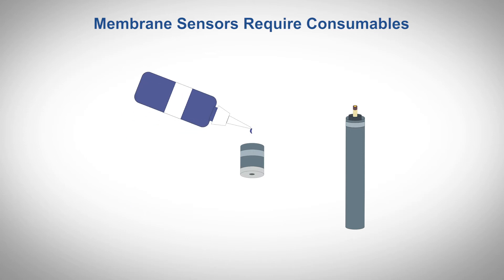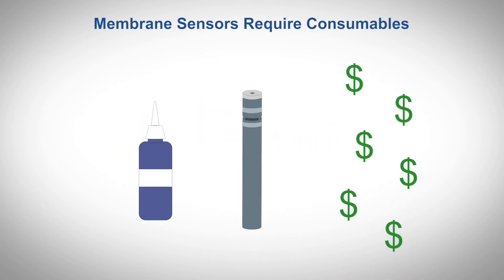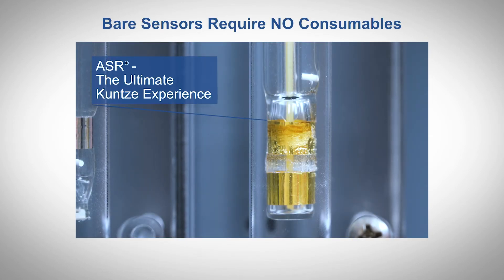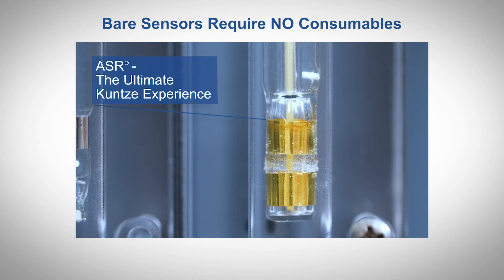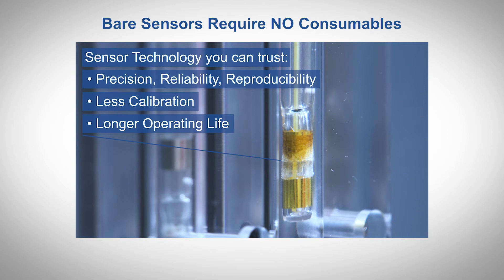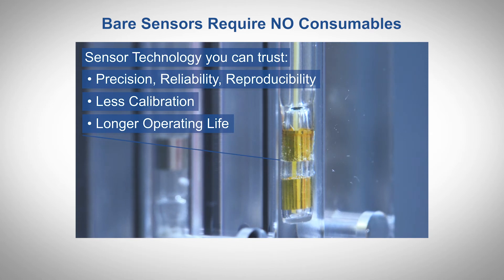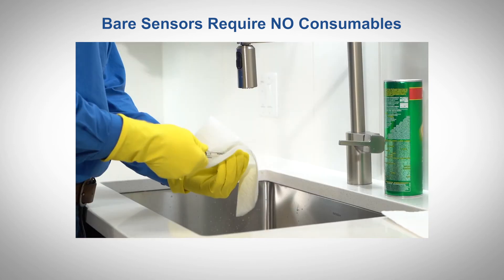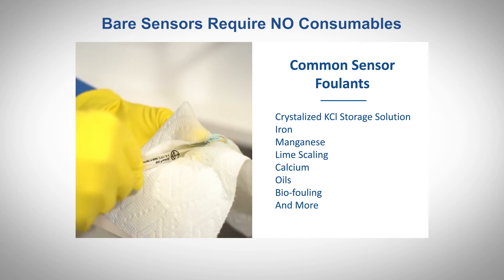Periodic refilling of the electrolytic gel over the reference and measuring electrode is also required. Kuntze's bare sensors do not require consumable components or reagents. They are low maintenance and have low lifecycle costs due to our patented ASR automatic sensor cleaning technology. The ASR function can be programmed to automatically clean the sensors as often as once a day as defined by the needs of the process. For significant fouling, Kuntze's bare sensors are robust enough to withstand manual cleaning with an abrasive detergent.